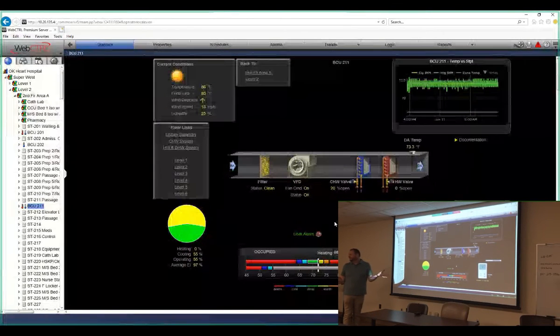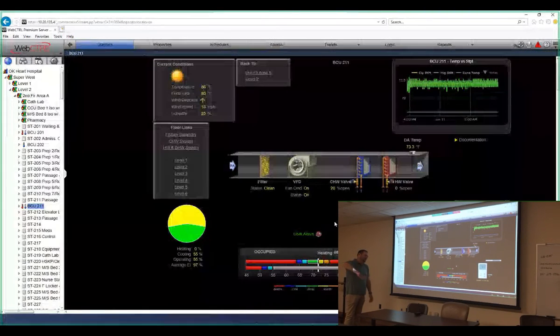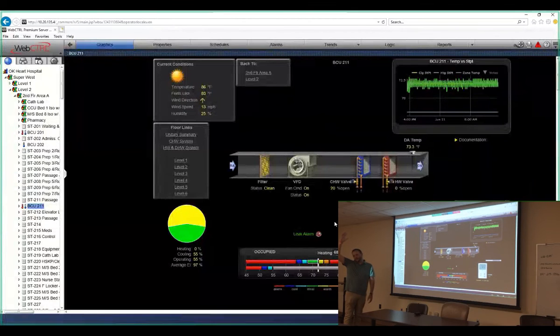Sequence-wise, they're simple, right? If temperature drops below the heating set point, we're going to start opening the hot water valve to try to get back up to the heating set point. Temperature goes above the cooling set point, chill water valve is going to open enough to bring it back down to the cooling set point. Simple. Fan runs all the time. Their fan doesn't cycle off. They run continuously. Then we monitor the status, the discharge temperature, and the filter status.